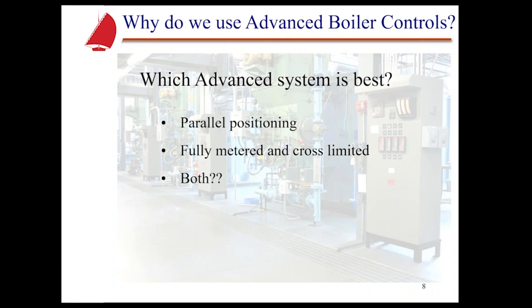And are there systems out there that can do both? Actually, Preferred Utilities builds a system that can do both. With a flip of a switch, you can go from fully metered and cross-limited to parallel positioning. And that's a huge advantage. If you lost, for instance, a flow meter, for whatever reason it was not working properly, with a flip of a switch, you could go to parallel positioning and go off of the feedback from the servos themselves. This can keep a system up and running. It's very, very critical, and it is a huge advantage.